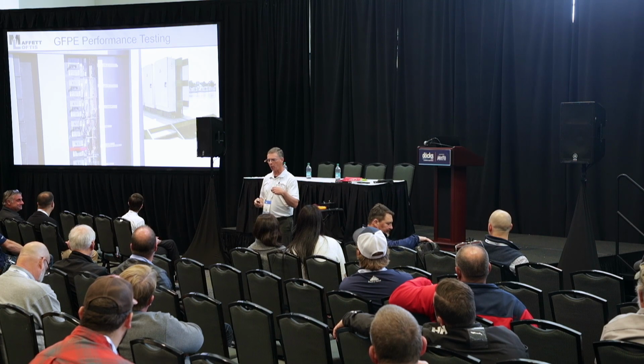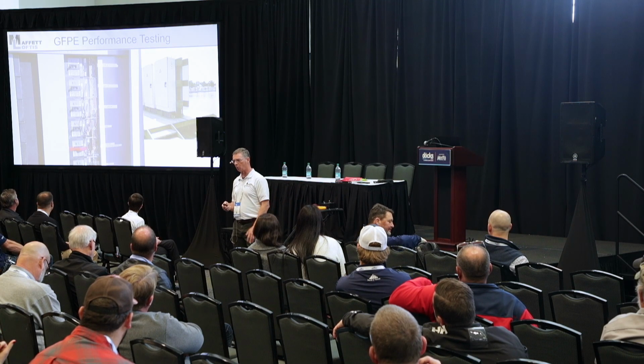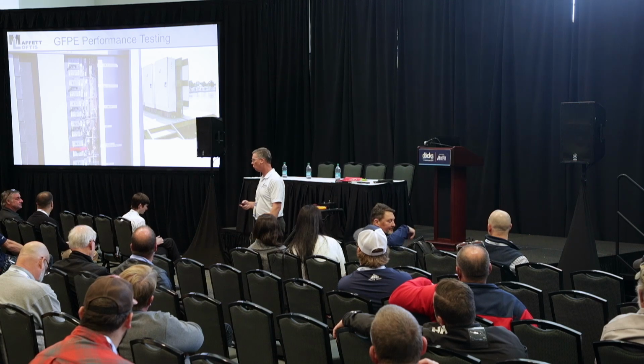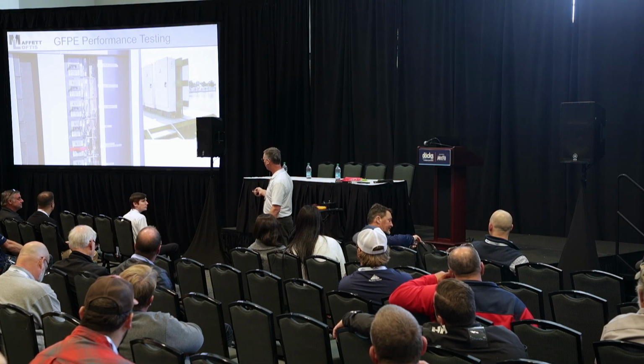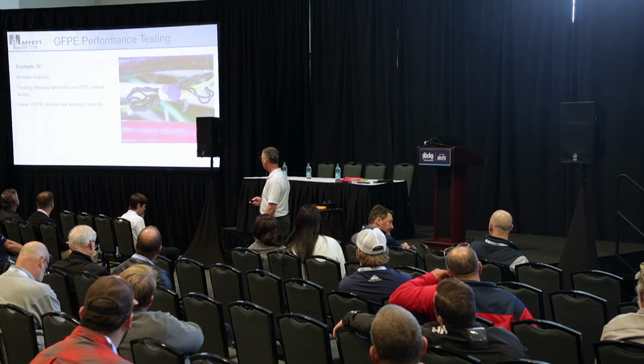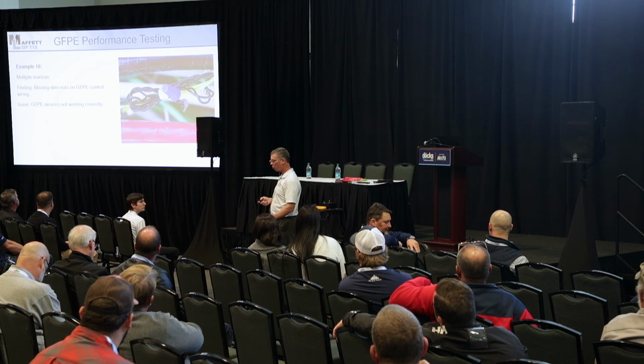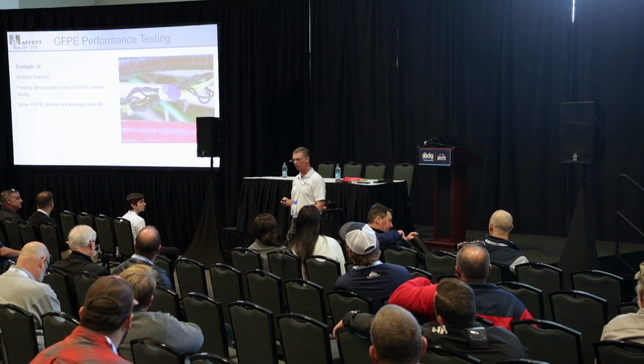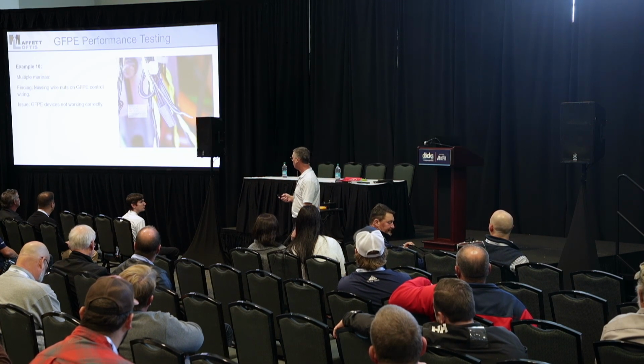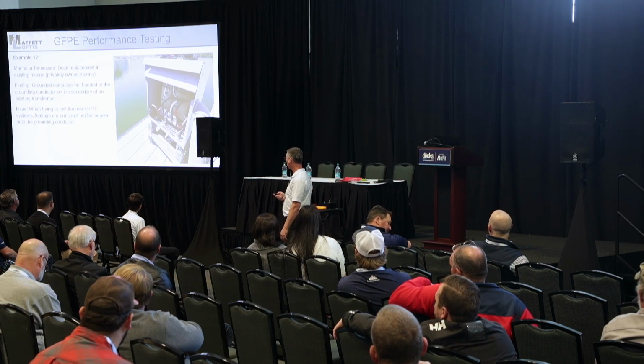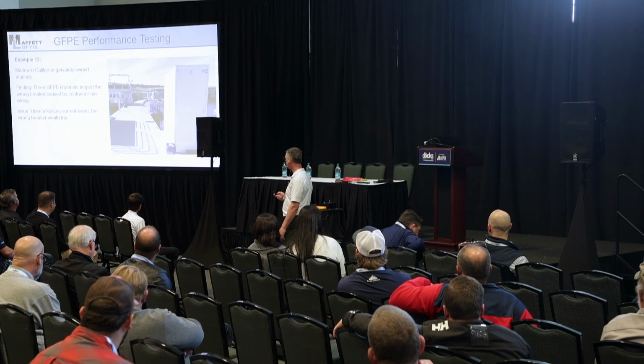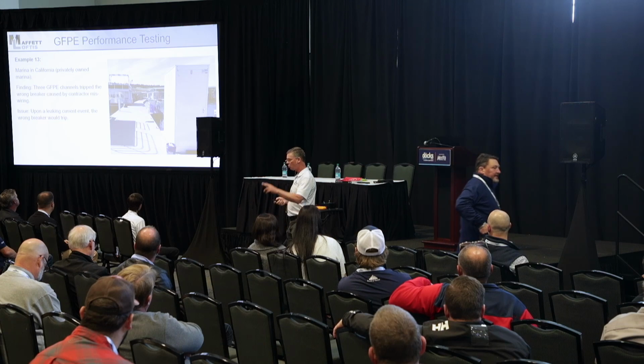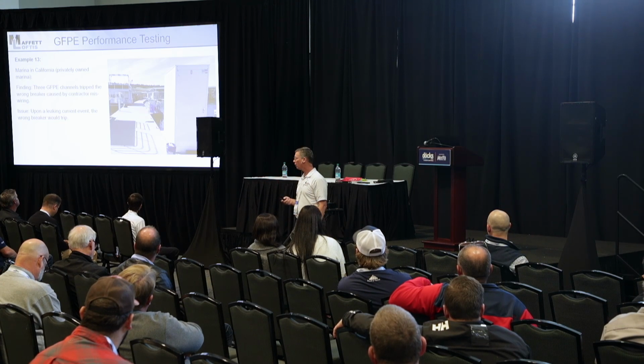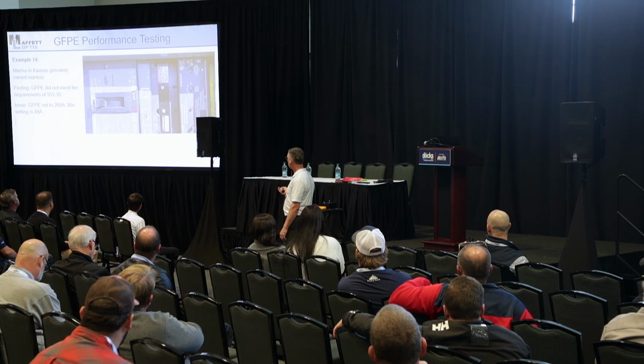They actually took the shunt trip breakers out so it wouldn't trip all the time because it wasn't fully coordinated and it was such a nuisance, couldn't keep power on. So they disabled the shunt trip breakers. Find all kinds of wire nut issues on the controls because if it's not working correctly, I find those. Issue after issue. Some circuits not wired. Here's a grounding issue on a transformer. This is another one that had swapped input outputs. And look at this GFPE device there.